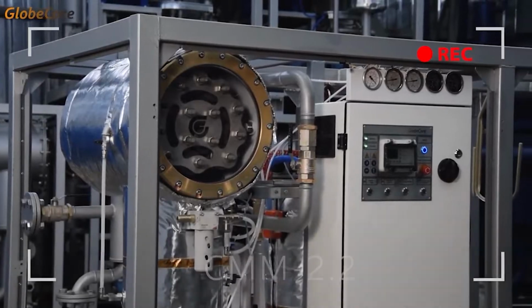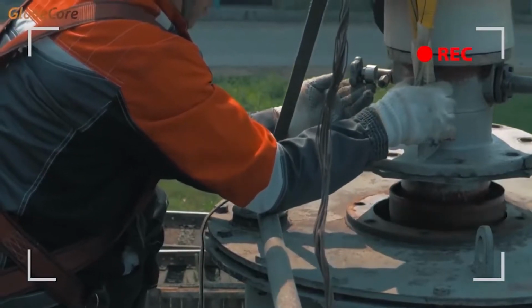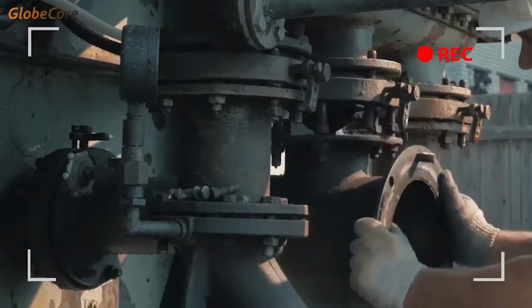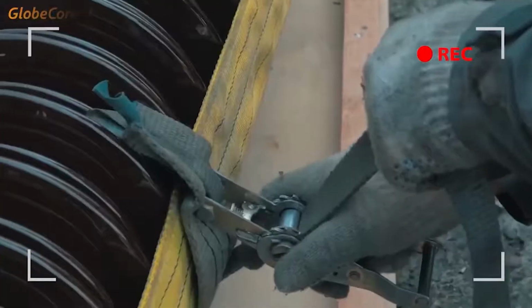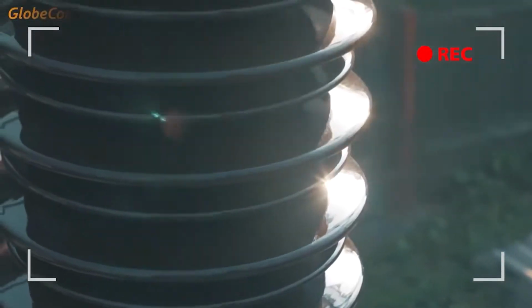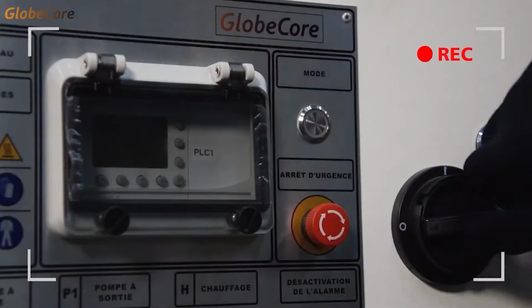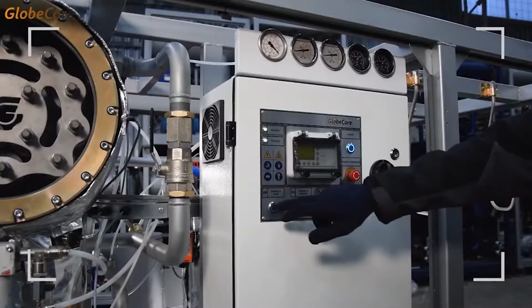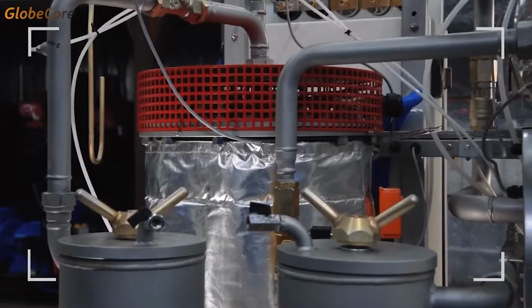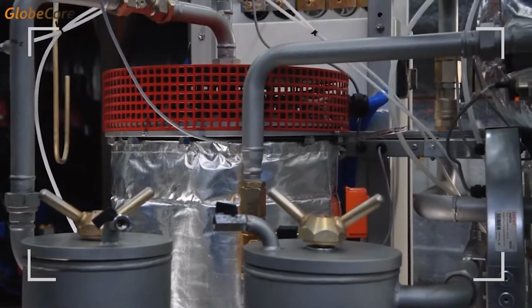During operation of a transformer, its oil becomes contaminated and moistened. Even a small quantity of moisture trapped by transformer oil lowers the oil's breakdown strength, so the oil needs to be dried. Detached paper insulation of windings and small suspended particles of carbon also need to be removed by a mechanical filter.